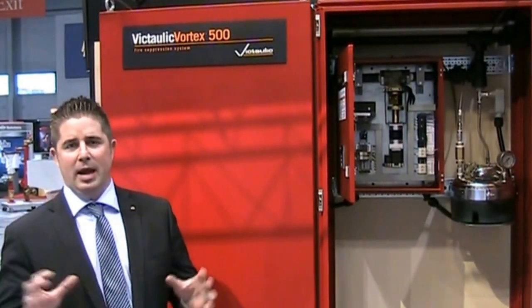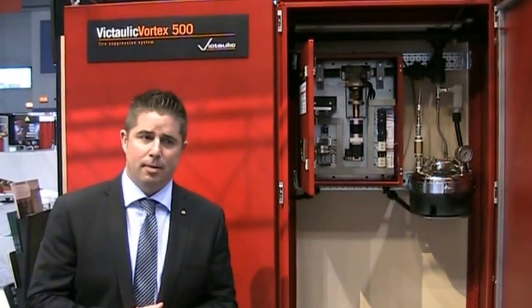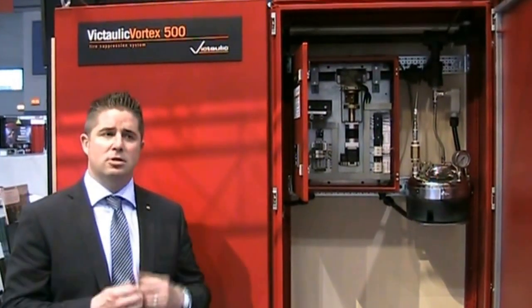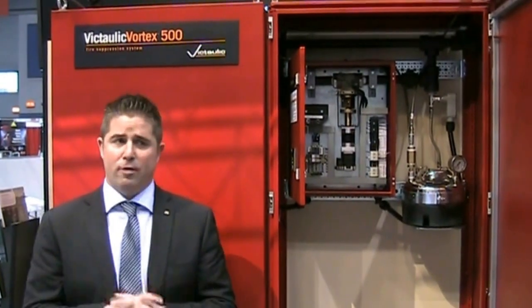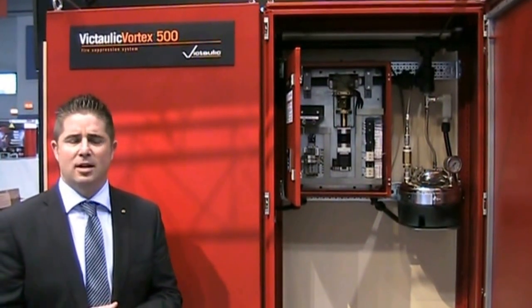The water also helps move the nitrogen around the room to create momentum. The Victaulic Vortex 500 system is our pre-engineered system for data center applications, motor control centers, and small server rooms, covering from about 600 to 4,500 cubic feet at sea level.